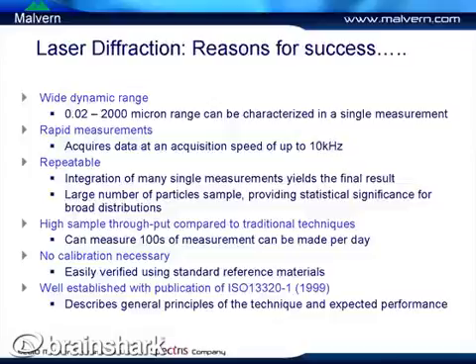We can make very rapid measurements with laser diffraction. Particularly the SprayTec instrument, which looks at dynamic events such as very short pulses of spray, can acquire data at rates of up to 10 kHz — so we can get a size distribution 10,000 times a second — and it allows you to look at short pulses in great detail.